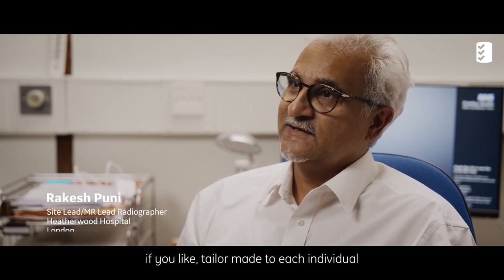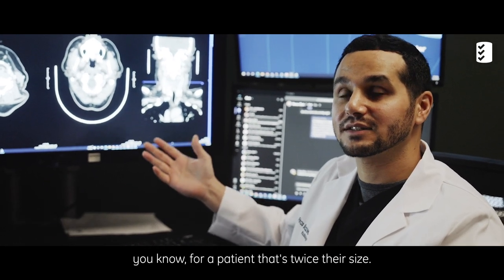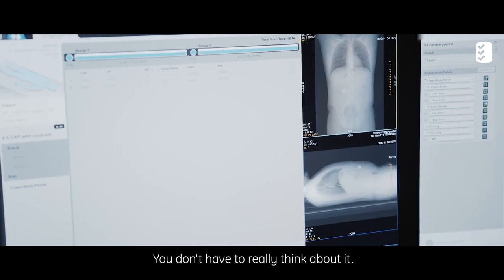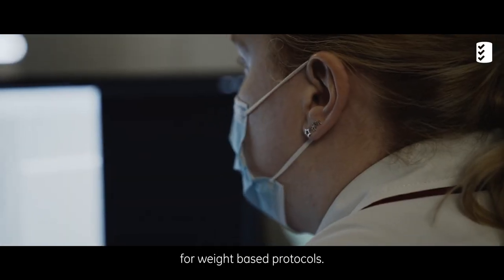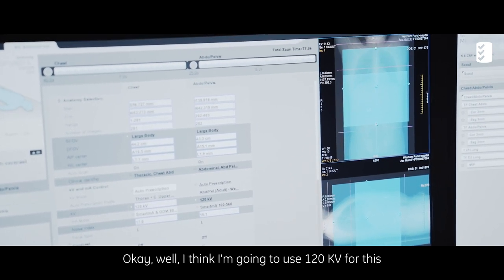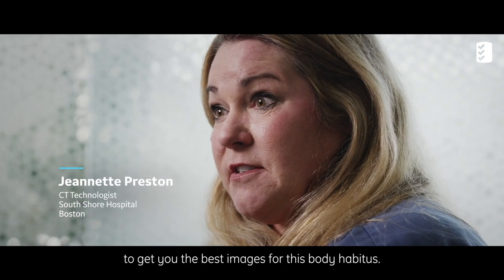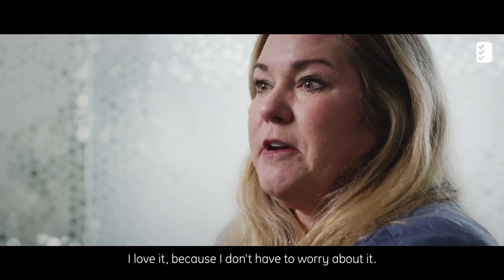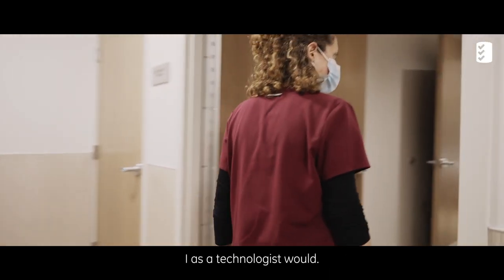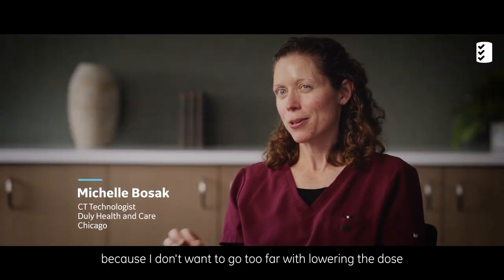Why should a thinner patient get the same dose as a patient twice their size? That doesn't make sense. Having auto prescription allows it to automatically do it for you — you don't have to really think about it. It has helped eliminate the need for weight-based protocols. It's so smart that it decides to use, for example, 120 KV and 0.8 rotations to get the best images for that body habitus. I love it, because I don't have to worry about it. This is probably dropping dose more than I as a technologist would, because I'm more hesitant — I'd rather give a little extra in the past.